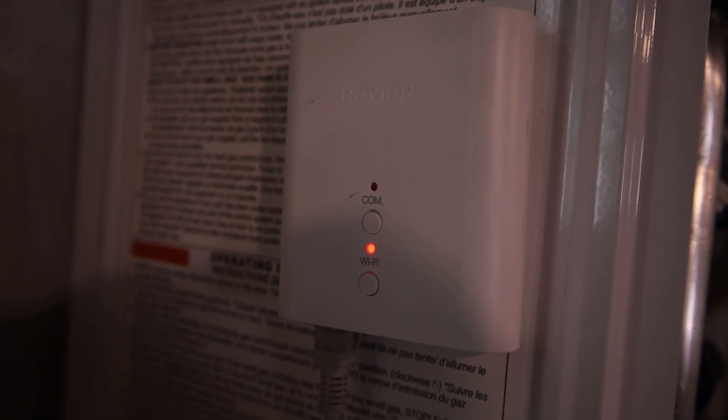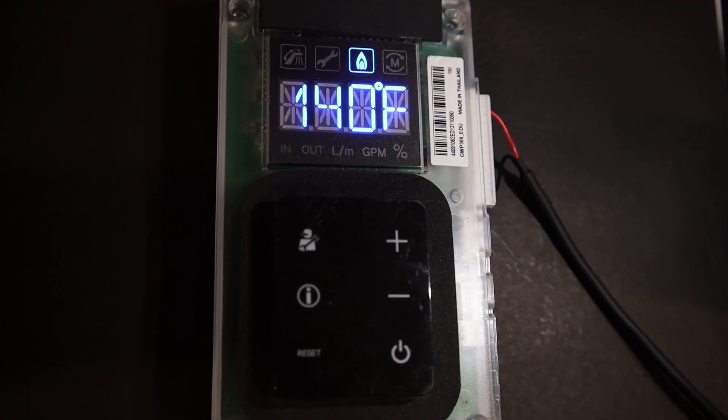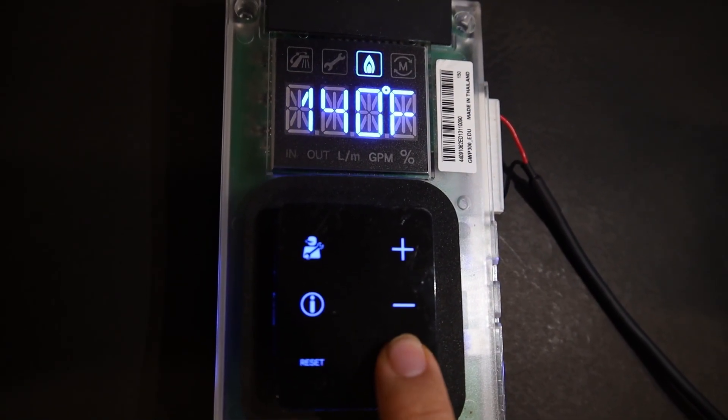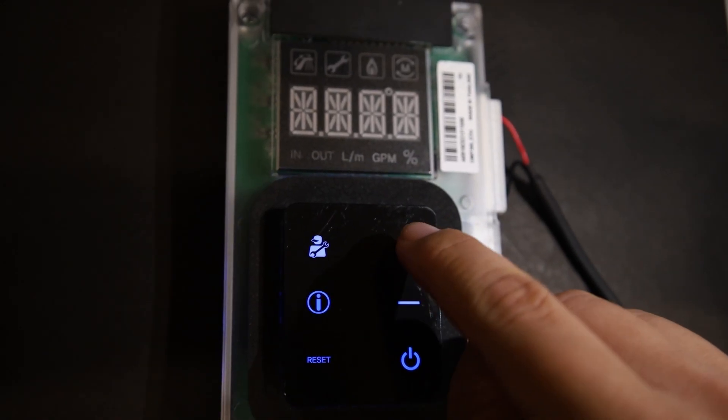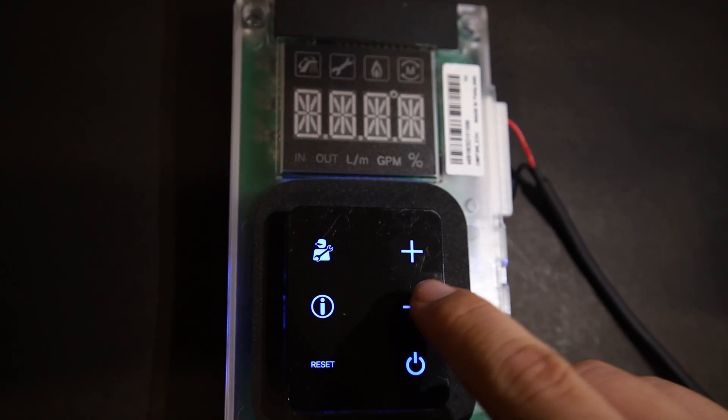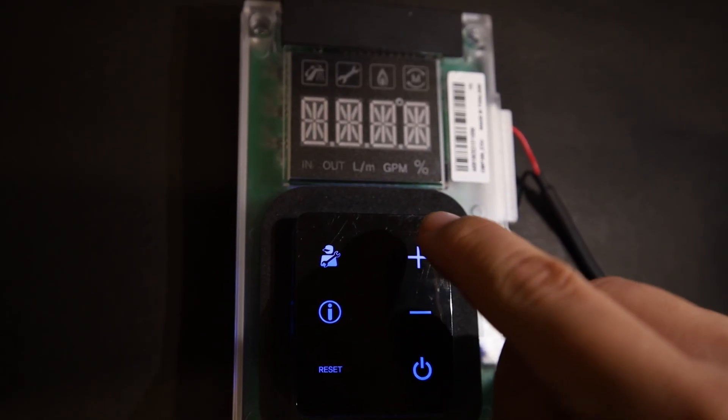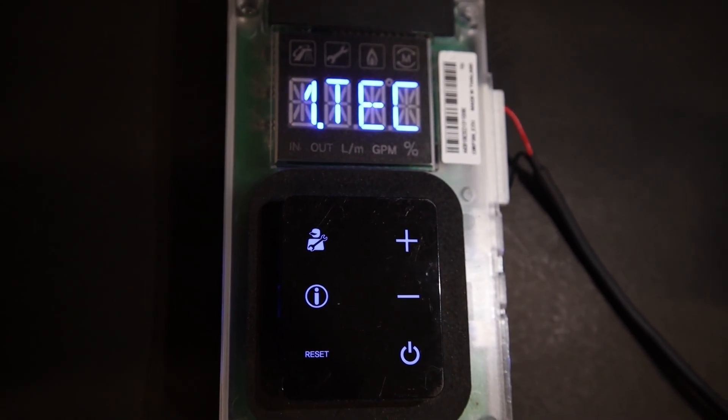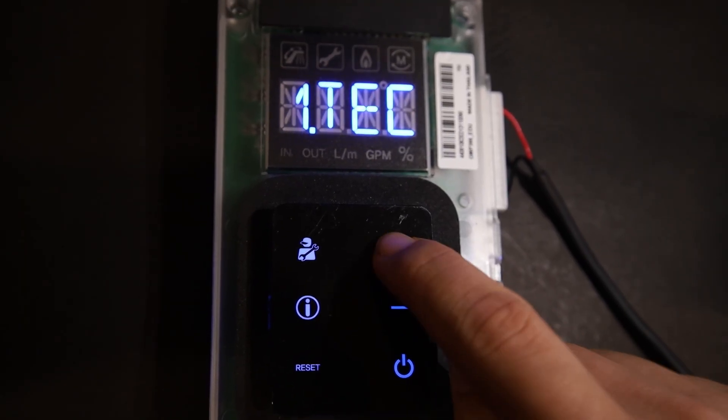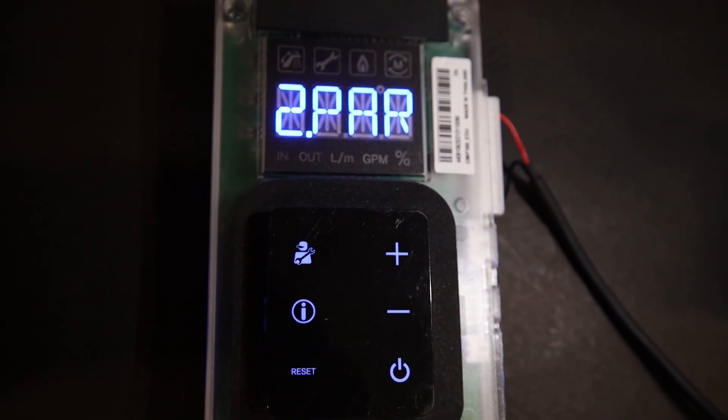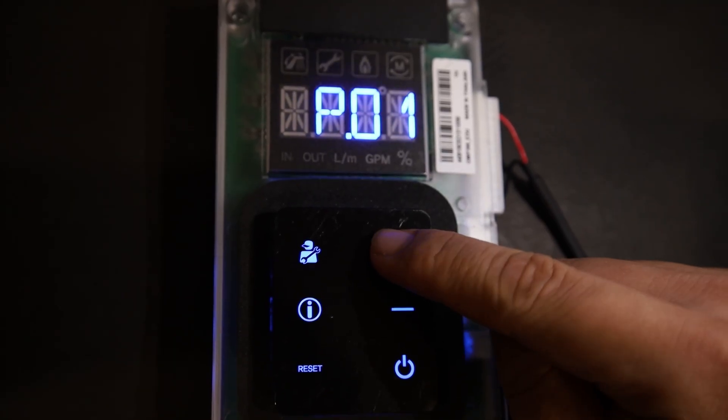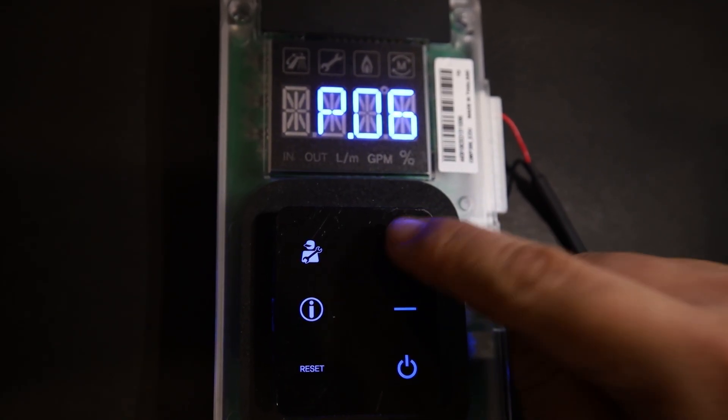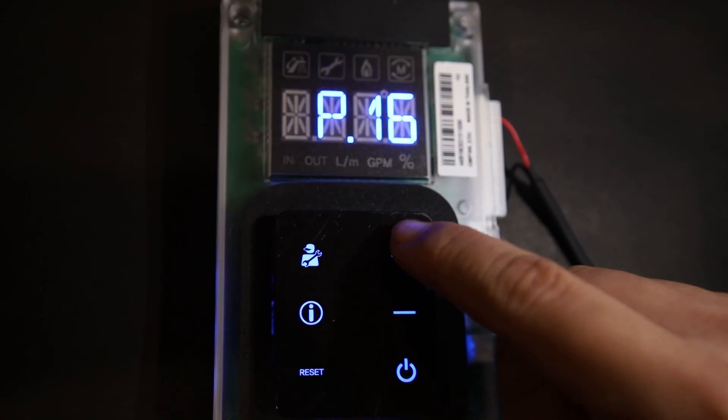Enabling these settings on the version 1 control is a little bit different. Turn the power off by holding the power button, press the plus button three times, the minus button three times, then the plus button four times. One dot TEC will pop up on your screen. Hit the plus button one time, then hit the circle with the i to get into this menu. You'll see a lot of parameter options, 32 in total, but just scroll until you see 18.